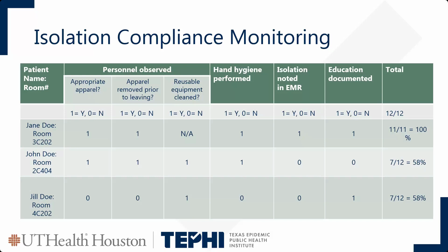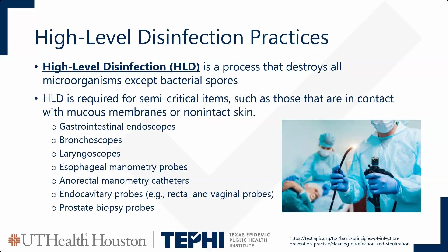So the next component that we're going to talk about is high-level disinfection practices. We briefly talked about this in Module 3, and HLD is required for semi-critical items, which are items that come in contact with mucous membranes or non-intact skin. Here's just an example of some items. Depending on your facility and your service line, you might have more or less. And like any good practice, we want to make sure that we're auditing to ensure that no harm is coming to our patients and things are being high-level disinfected appropriately and according to the instructions for use, or IFU.